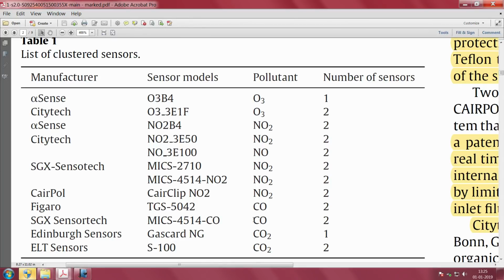So you can see this issue of multiple gases from the same sensor is evident. Take MICS-4514 - you can measure carbon monoxide, as well as nitrogen dioxide, both from the same sensor. You will have two sensing elements: one takes care of oxidation, the other takes care of reduction, and in the process it is able to measure both these parameters on the same sensor.